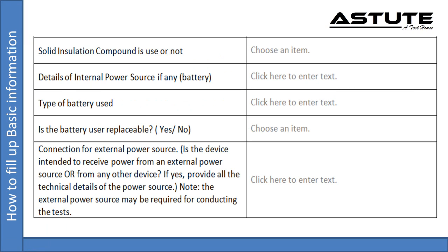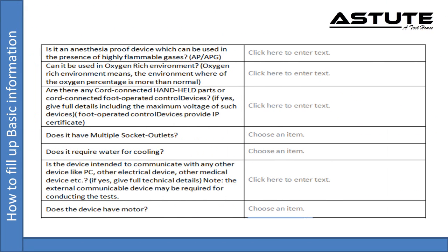Please submit us the details of the battery. Please submit us the details of the category AP and APG. Category AP is related to rating for ME equipment or an ME equipment part complying with specified requirements on construction, marking, and documentation, in order to avoid sources of ignition in a flammable anesthetic mixture with air.